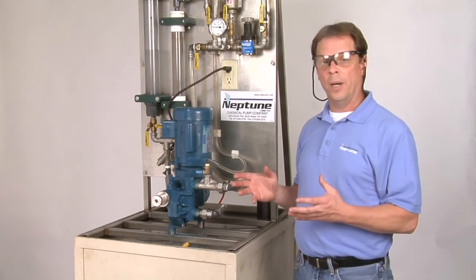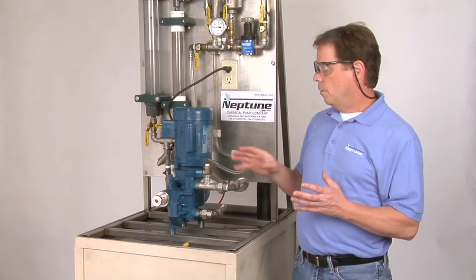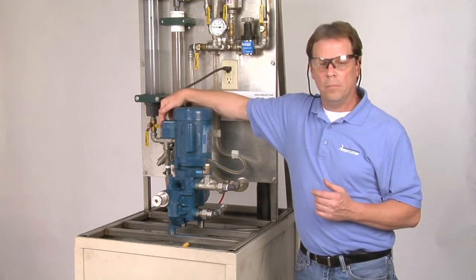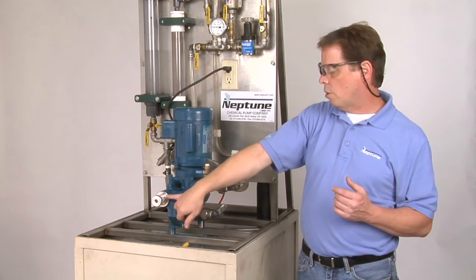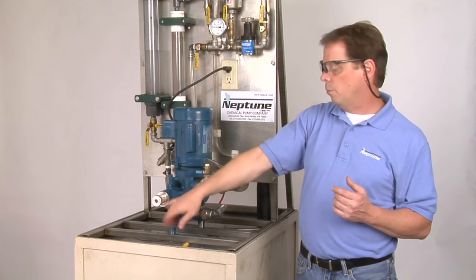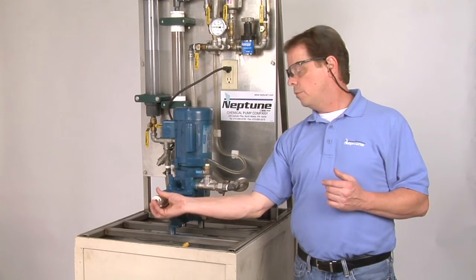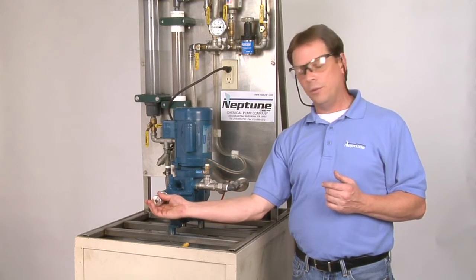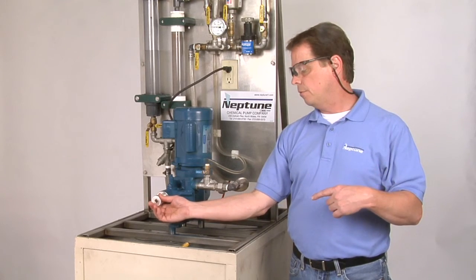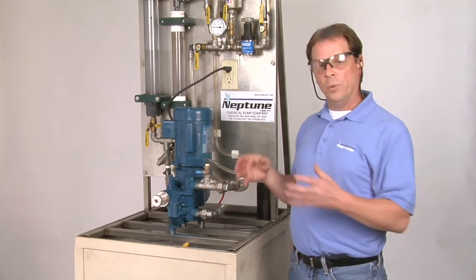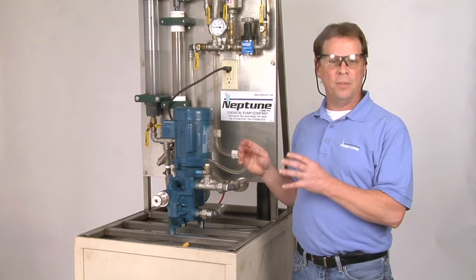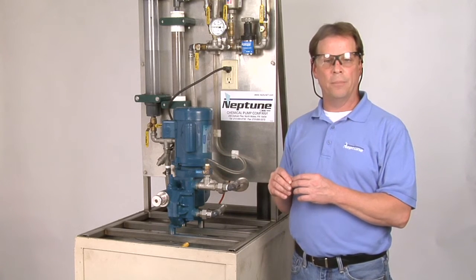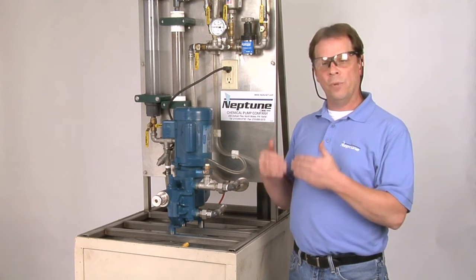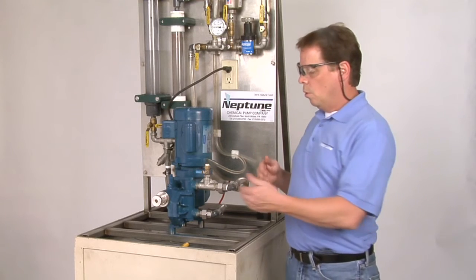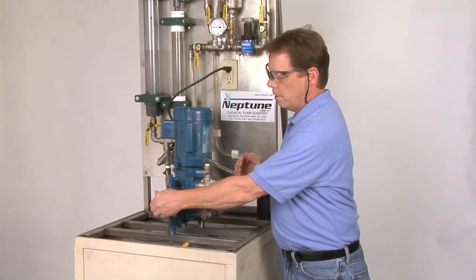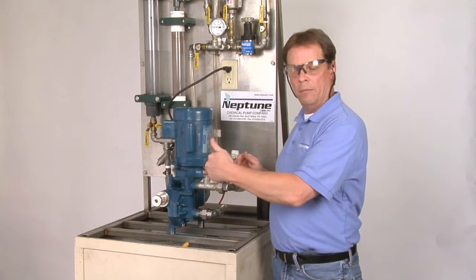Next, we want to start the pump. We start the motor up on 0 stroke, which is the micrometer dial all the way out to 0, counterclockwise. Now what we typically do is let the pump run for 5 to 10 minutes on that 0 setting. Once you go through that time frame, we adjust the knob to a setting.